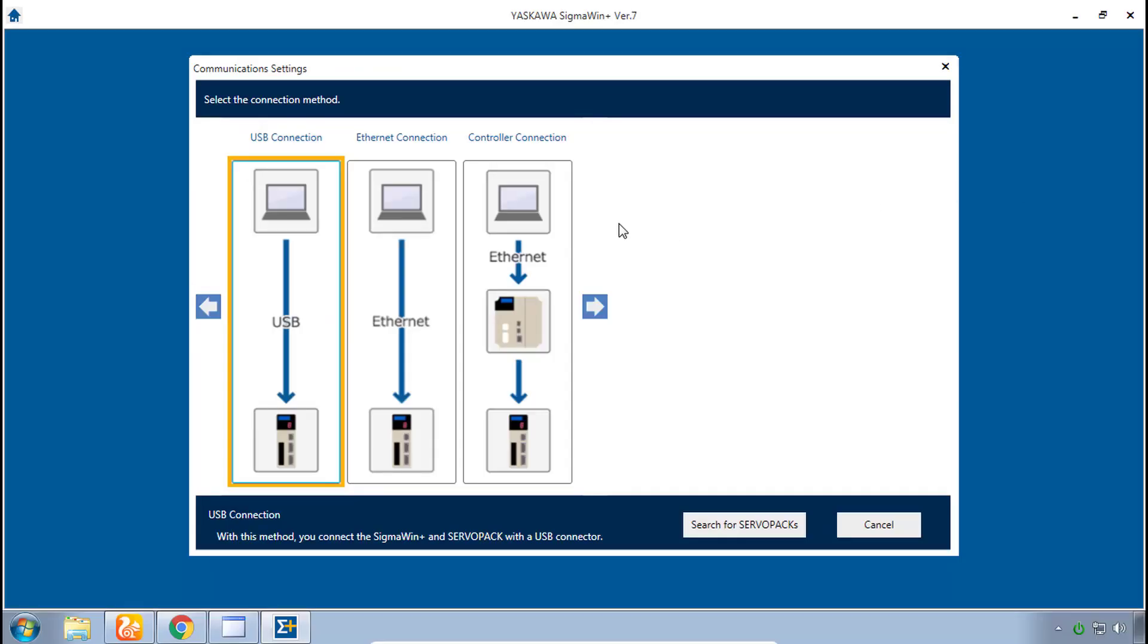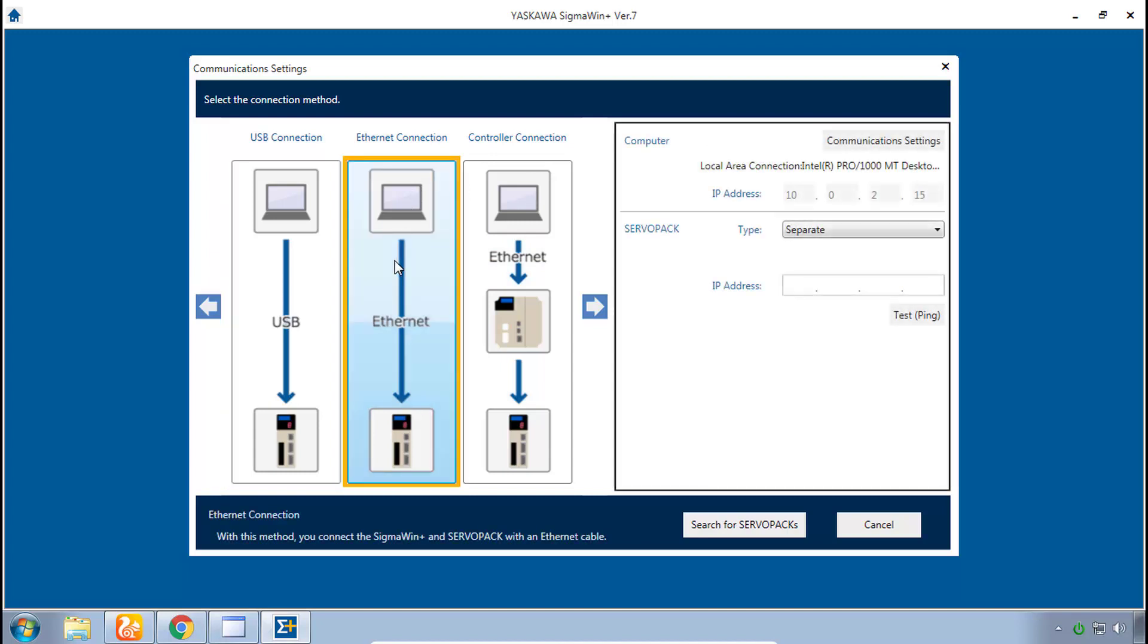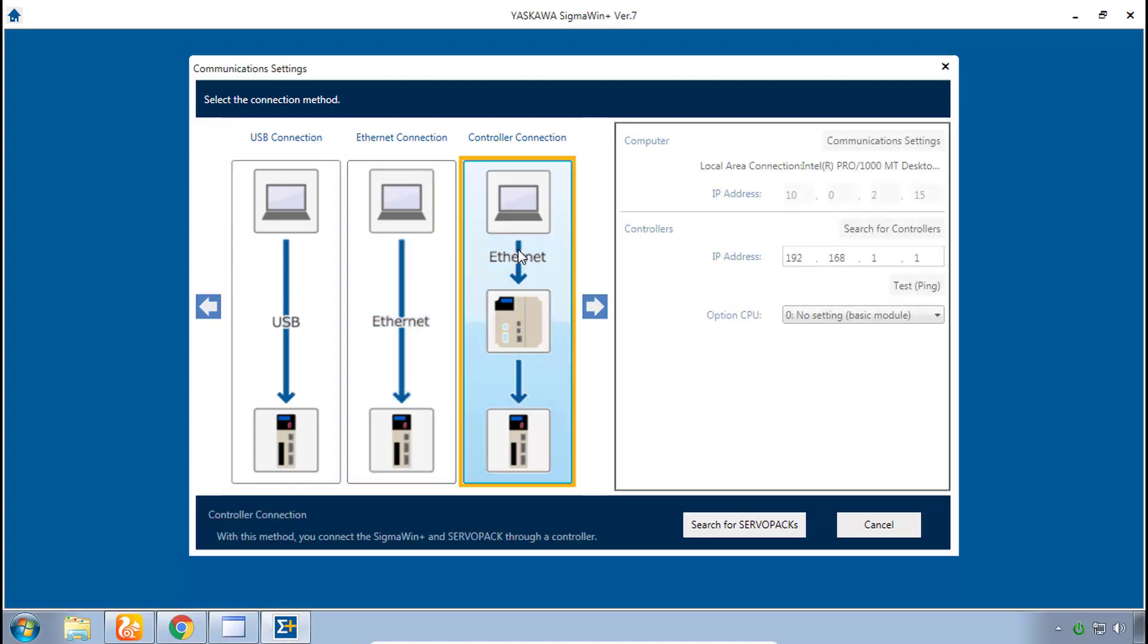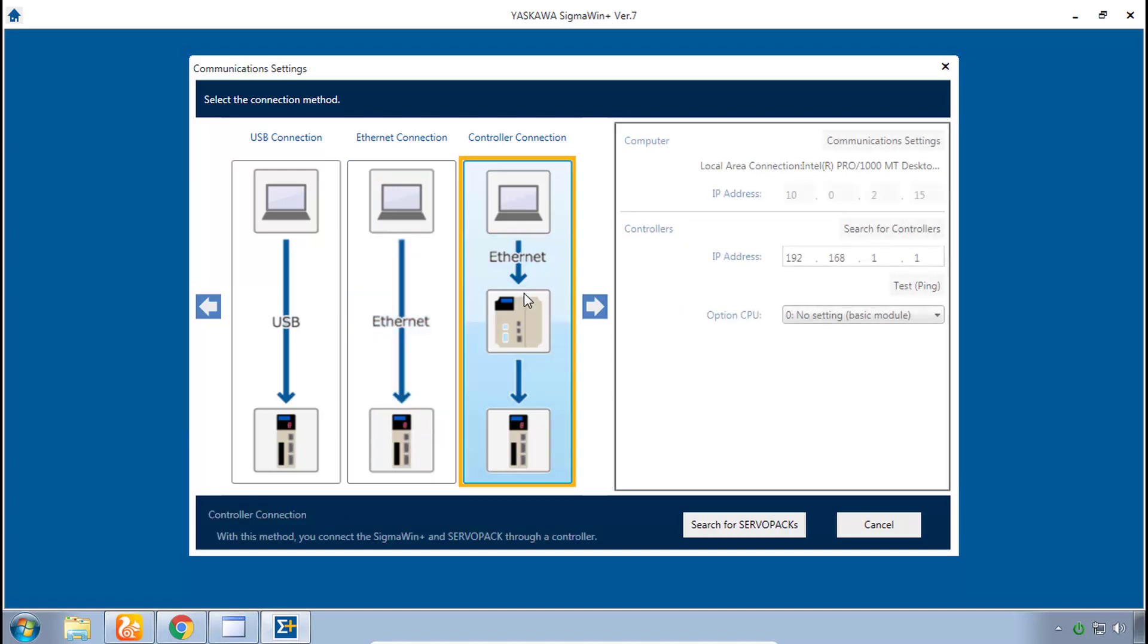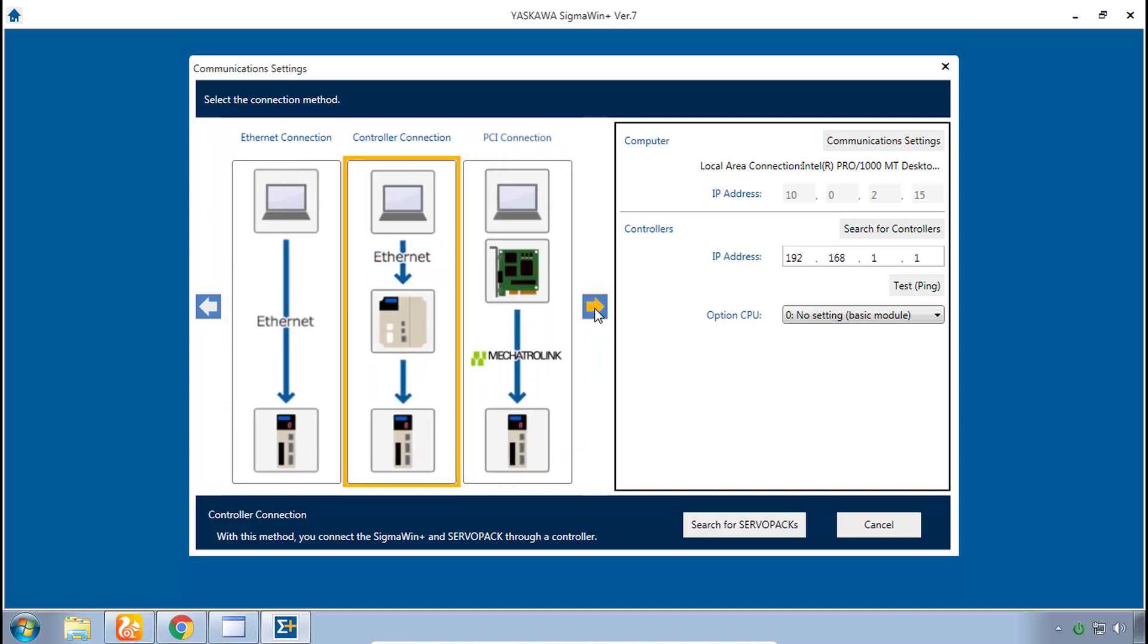So back in Sigma Win Plus you might think okay we need Ethernet connection or you might even want to try controller connection. However, as you look at these graphics carefully you do see that Ethernet connection means a direct Ethernet connection to the servo itself and controller connection is specifically for the standard MP series controllers not the IEC series controllers. So let's keep scrolling here to the right.